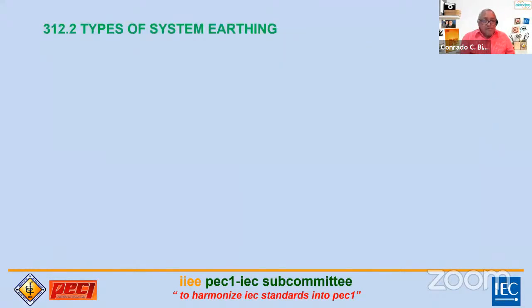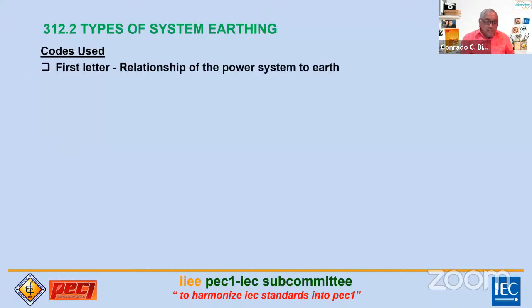Now we have types of system earthing. Earlier we discussed earthing and grounding systems. In IEC, we will often hear about systems earthing. What are the codes used in IEC standards? When you discuss things with engineers familiar with IEC, they will talk about types of earthing using certain codes. In the PEC, there are only two terms: grounded system and ungrounded system. But in IEC, it's almost the same, but they use codes to better understand the relationship of the installation.